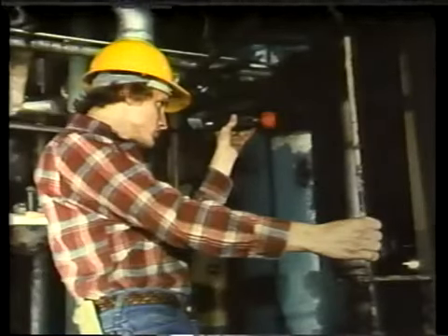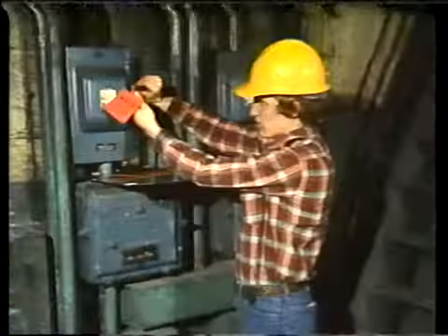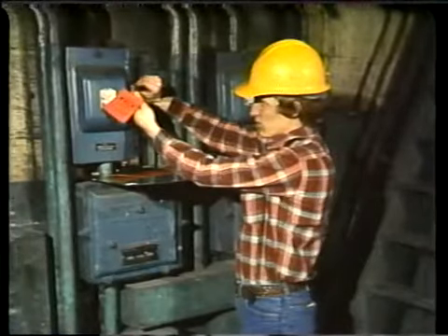As a double check of your lineup, you can physically trace a mechanical system to see what has to be tagged out. When a complete list of what has to be tagged out has been drawn up, it has to be approved by an operations supervisor. This is one more check to ensure that it's right, and it keeps operators informed of the status of their equipment.